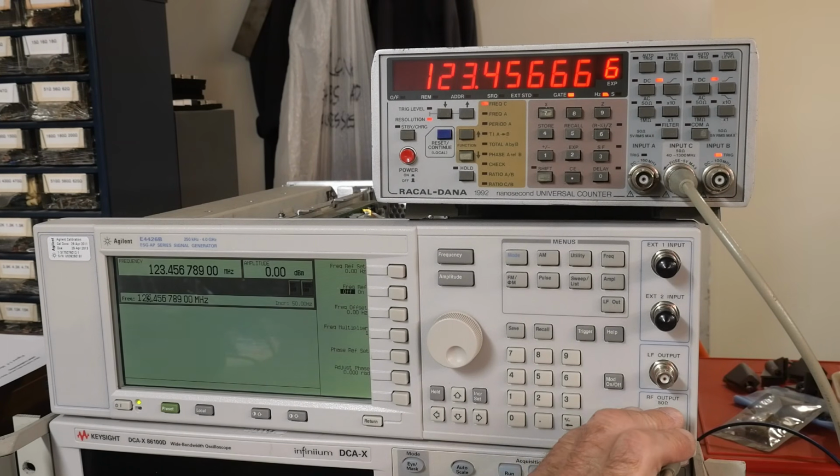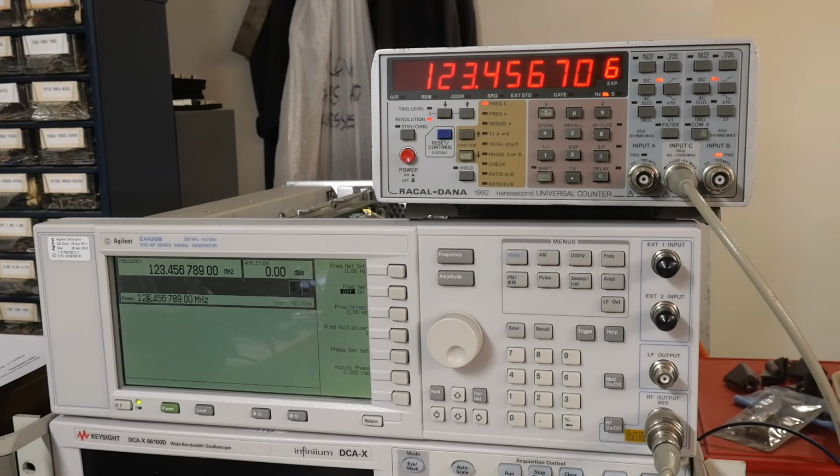Did I push the magic button? Did I make it work? I don't know. I was poking around, and there is calibration software available for this machine. There's no front panel calibration, but there is over-the-bus calibration. And Agilent gave the source out there. You can download it from the Agilent website, or Keysight now website. But you would have to have an XP computer with a particular HPIB card in it to make it work.